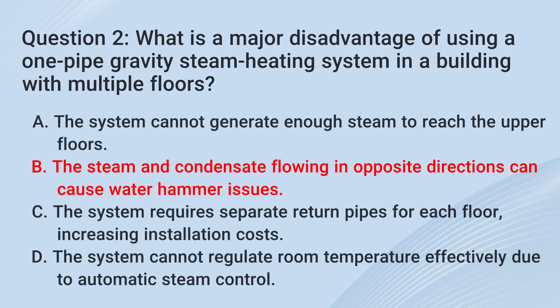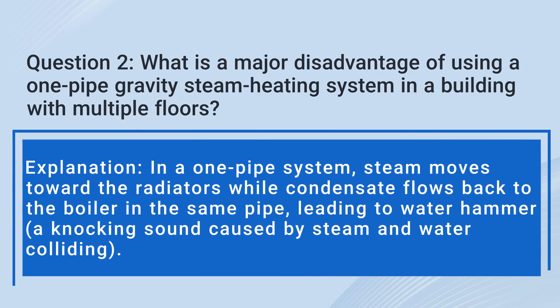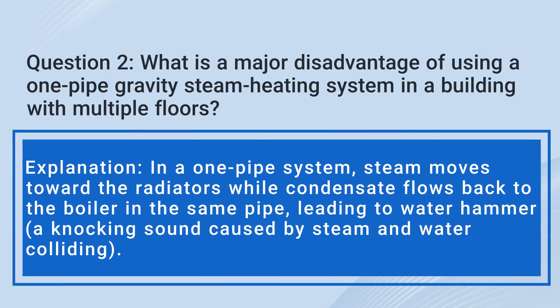The correct answer is B. The steam and condensate flowing in opposite directions can cause water hammer issues. In a one-pipe system, steam moves toward the radiators while condensate flows back to the boiler in the same pipe, leading to water hammer — a knocking sound caused by steam and water colliding.